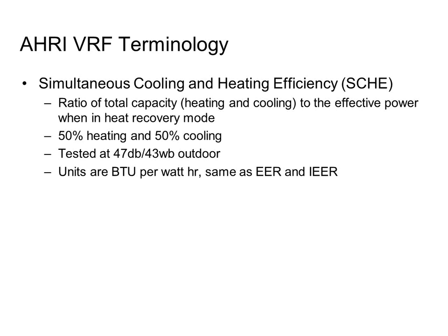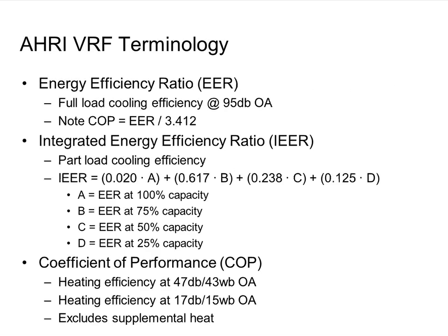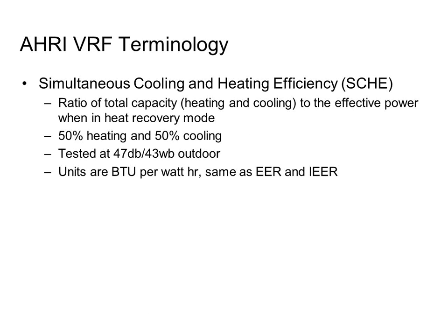The units of measure for SCHE are BTUs per watt hour, which is the exact same as the units we use for EER and IEER. So if you want to convert SCHE to a COP at that instant in time, you would use that same formula I showed you before. The COP would be the SCHE number divided by 3.4. That would give you the COP, right? So that's kind of your best case scenario.